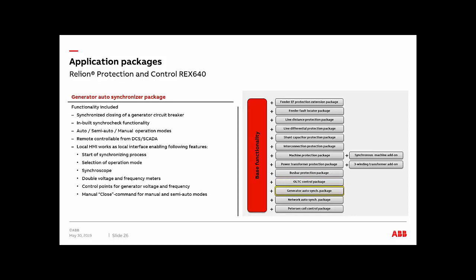So moving on to the generator application, the auto synchronizer package. On this one, you do have synchronized closing of a generator. This is included in this package. There is an inbuilt synchro check functionality. You do have the option of having this auto synchronizer in automatic, semi-automatic, or manual operations. You can do control from SCADA as well, or DCS.